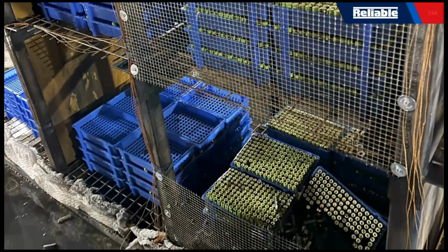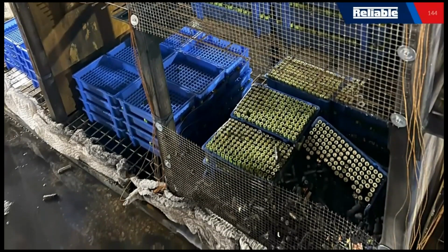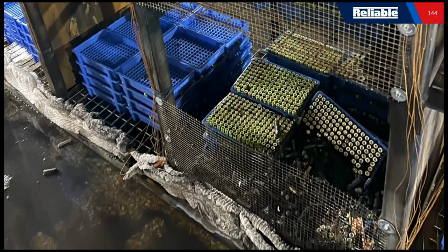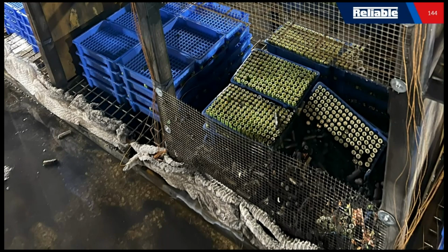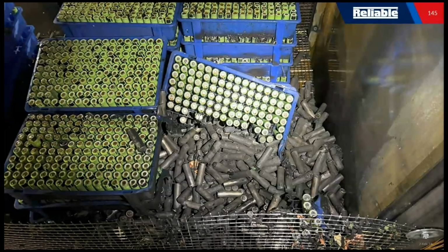We were able to start the thermal runaway, cell-to-cell propagation, and then through the process of our sprinkler wetting it, stop that. We only consumed about half of the cells located in the bottom of the rack. So it's a very exciting sprinkler product, and it's really the only solution that is out there based upon test data. And until the laboratory partners have a way to identify some way to test lithium-ion batteries, this is really where we're at.